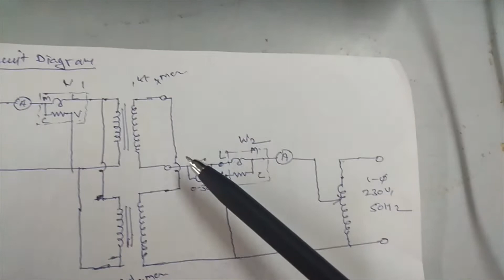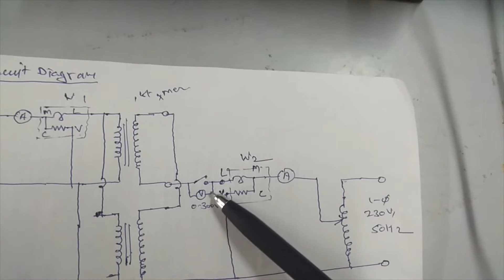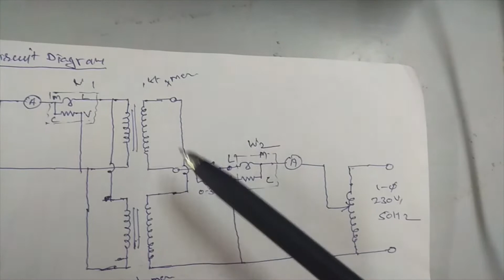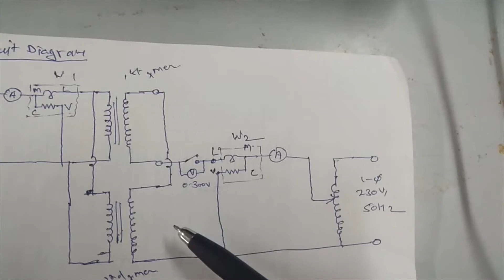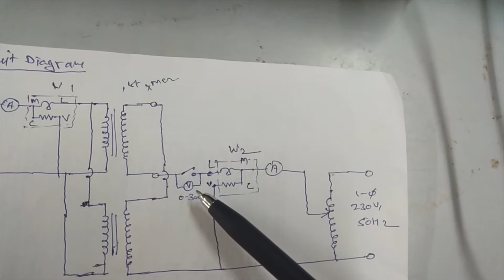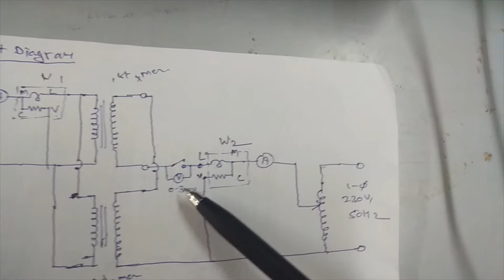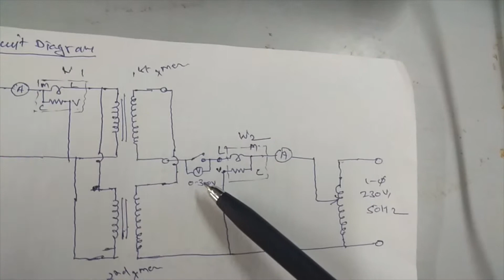Here we have used one switch, and across that, one voltmeter is connected. This voltmeter identifies whether the secondaries of the two transformers, connected in series, are in phase opposition or not. If this voltmeter reads 0, it means they are connected in series in phase opposition. If it gives some value, it indicates they are not in phase opposition, and the connection needs to be reversed.